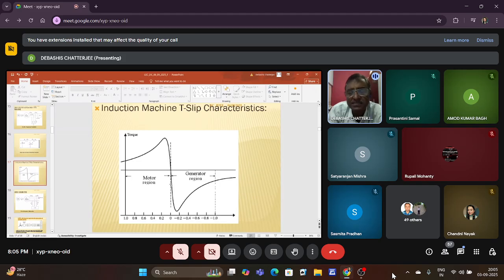And if there is an increase in speed, the power will increase, but at the same time, slip is also increasing, and that extra power will result in excessive current from the stator terminals, and the generator will be heated. So you cannot have additional power generated beyond the rating, say for a 1 kilowatt generator. If you try to generate 1.5 kilowatt, naturally the current will increase, and the machine will burn. Therefore, it will generate appreciable power at a speed around 1560 RPM.